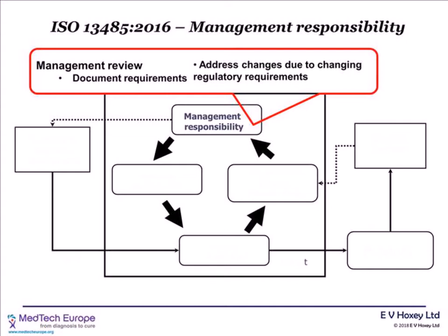Moving on to look at some of the requirements for management responsibility. Some of the requirements in the standard around management review have been updated, particularly around documentation and addressing changing regulatory requirements. So on this slide, I've just highlighted some of the new inputs that are now explicitly required for management review. So management review has to include information from complaint handling, reporting to regulatory authorities, audits, be they internal or external audits, process monitoring and product monitoring. So effectively now what's been done is that the inputs to management review reflect the topics in the measurement, analysis and improvement section in Clause 8. Previously, some of the requirements in 8 were required to be inputs into management review, but not all of them, and now it's been made consistent.